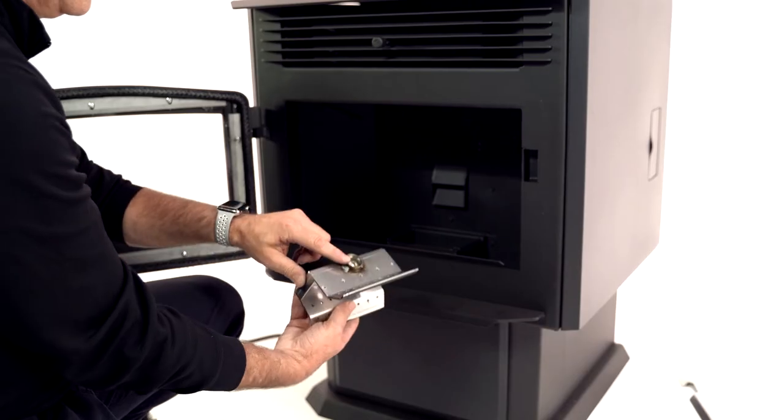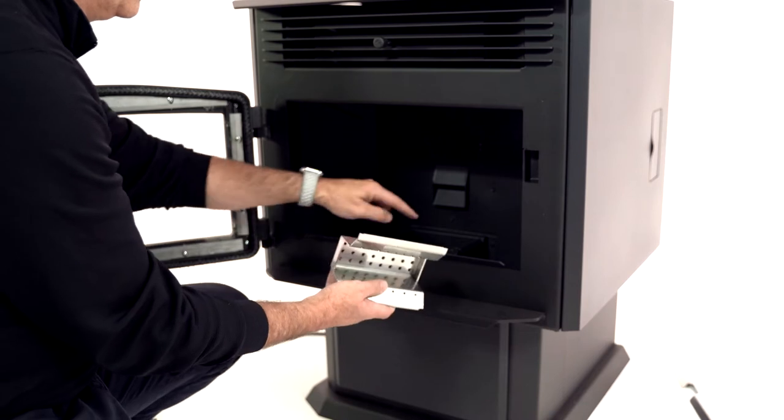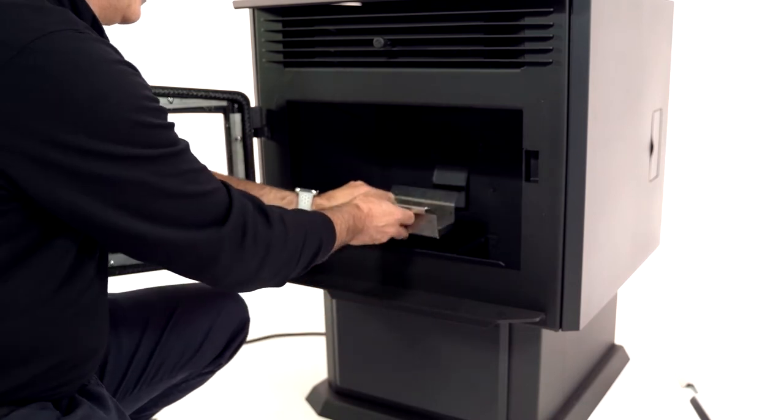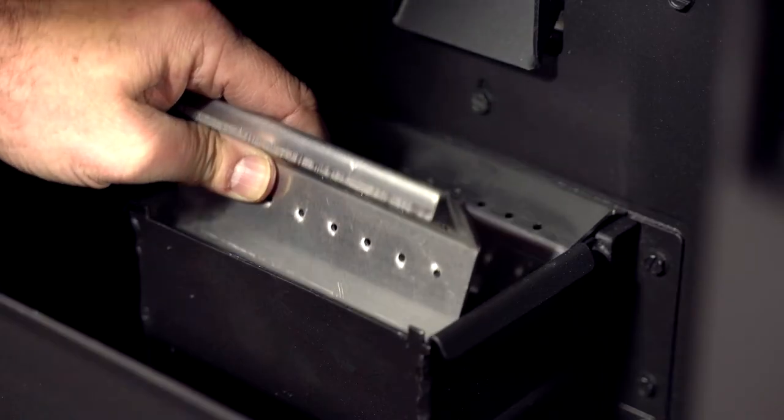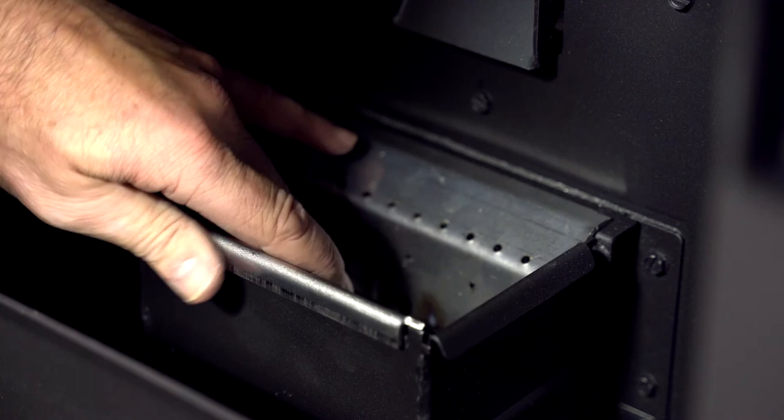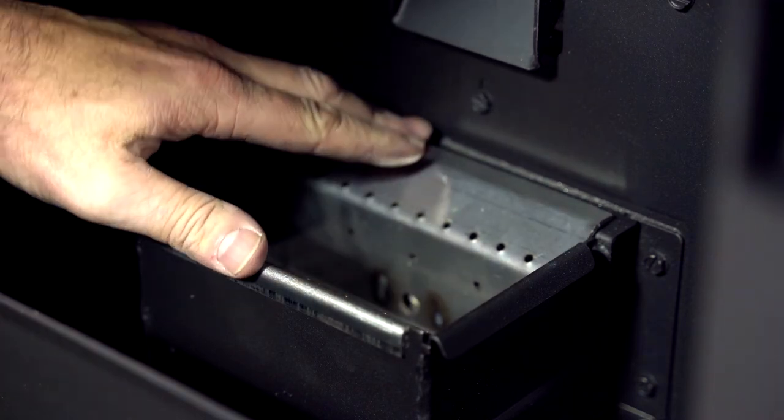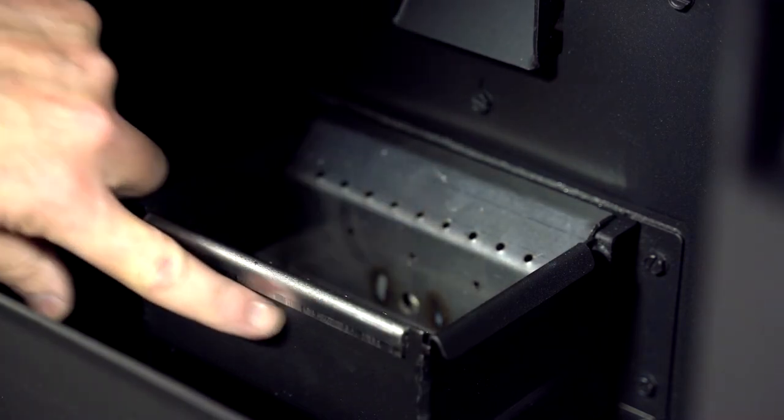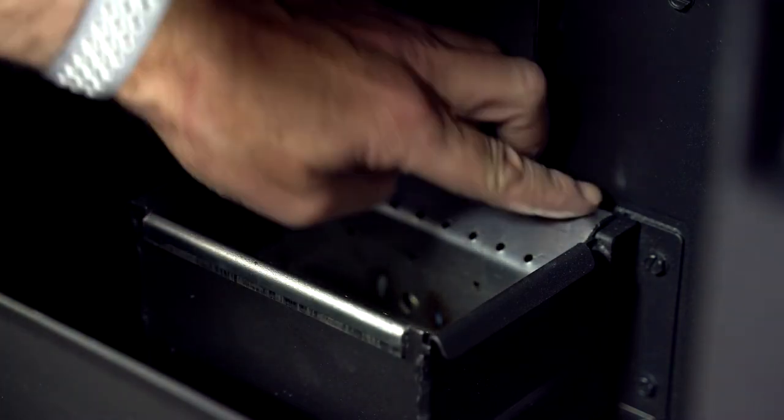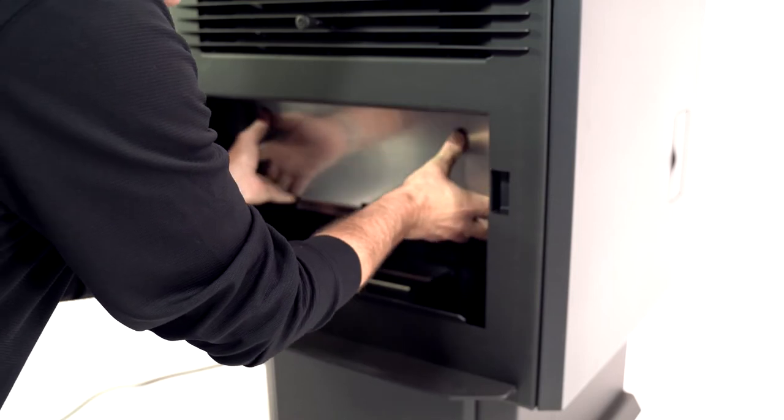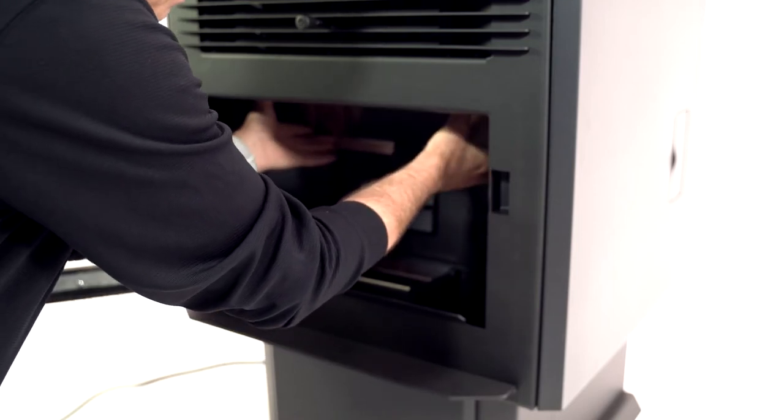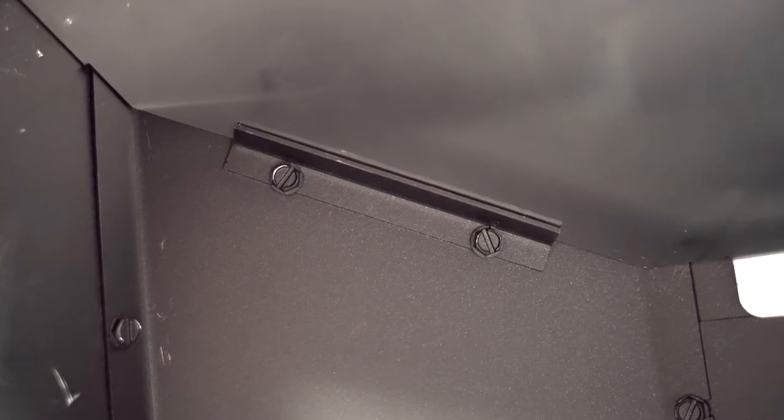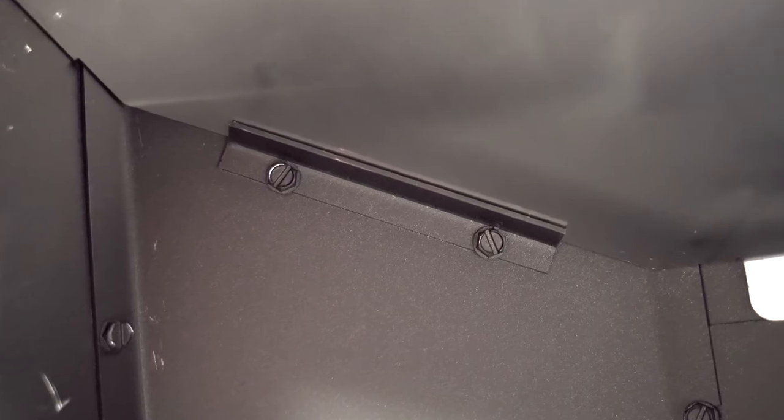Put the fire pot back in place and make sure that the front and back of the pot are firmly seated on the pot receptacle. A burn pot not well positioned negatively affects combustion. Reinstall the baffle and make sure it rests on the side angled brackets and touches the back of the firebox.